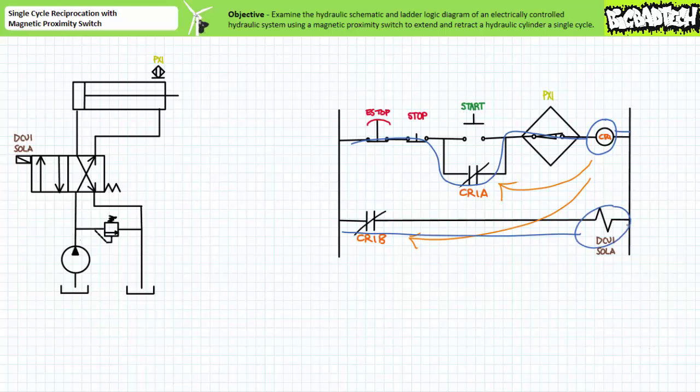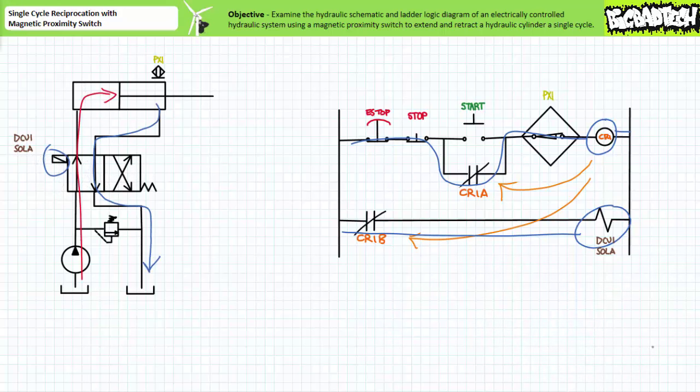In our third rung via the closed CR1B contact, DCV1 Sol A energizes. On the hydraulic side the solenoid actuated valve moves the spool to the straight-through position and pressurized flow enters the cap end. The cylinder starts extending. It will stay in this state until the extending piston face enters the operating point of magnetic proximity switch PX1.